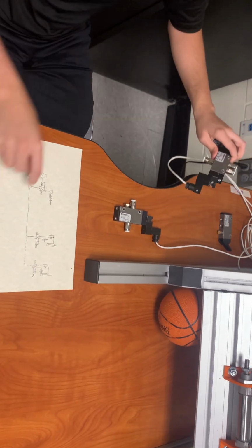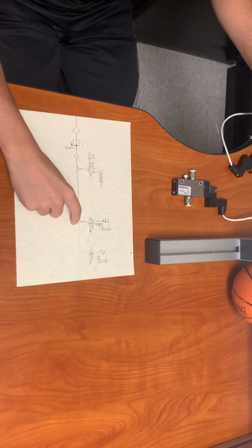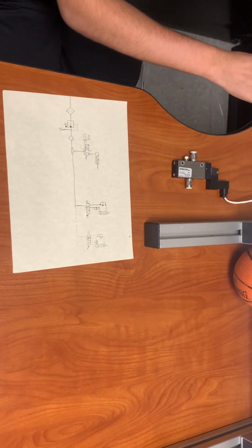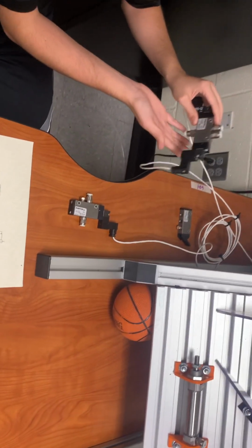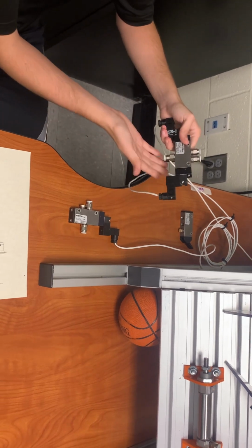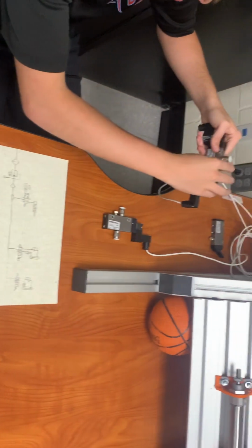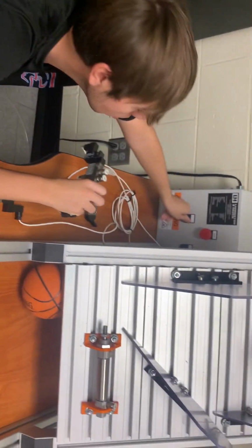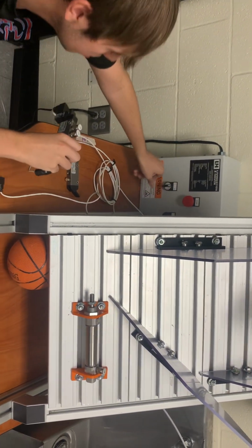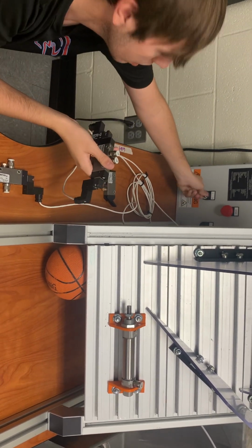Next, if we go back down the T-port and go to this side of it, we follow it to our 5-port valve, with 3 ports on the bottom and an A and B port on top. This is our supply port right here. The supply leads us to our number 2 port, which when we switch it to number 1, our cylinder goes up. When we switch it to number 2, the air goes down our number 4 port and the cylinder goes down.